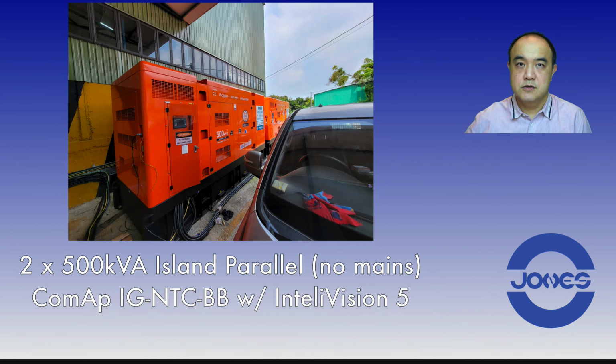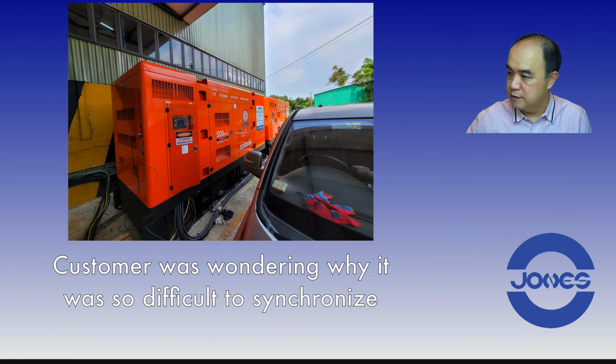So, I was testing two 500 kVA rental gensets under island parallel situation, meaning there's no mains, only the two sets in parallel together, using ComAp's IG-NTC-BB controller with an InteliVision 5 color display. So you can see these orange gensets working outside the factory. And the customer was wondering why the gensets were so difficult to synchronize. They were having trouble getting synchronization every time.